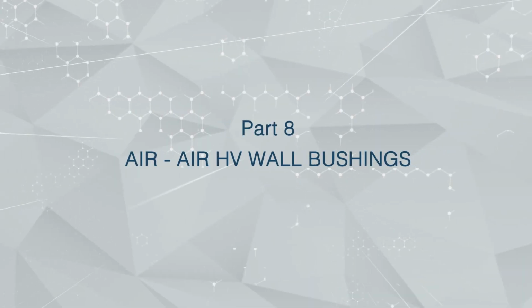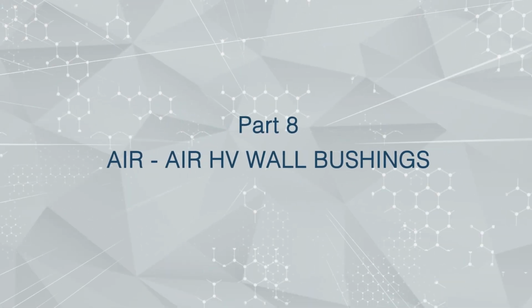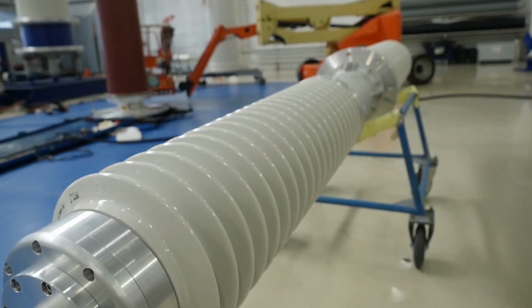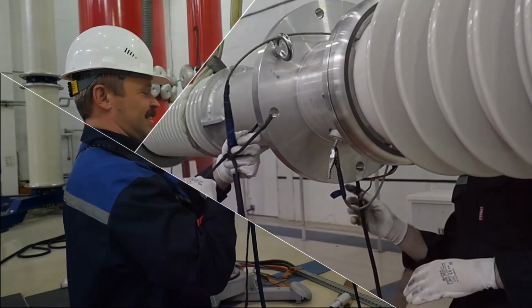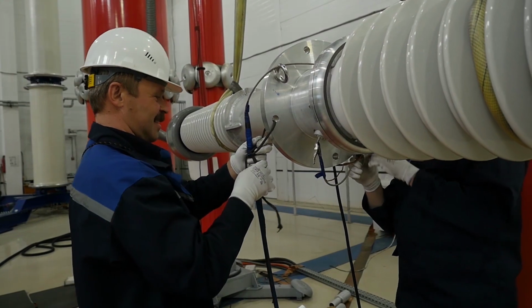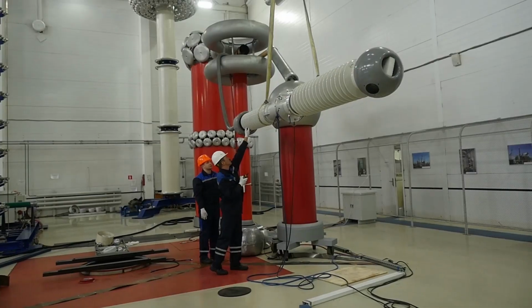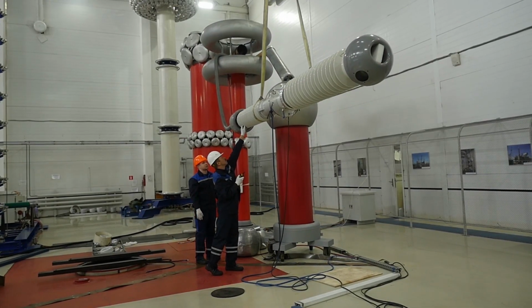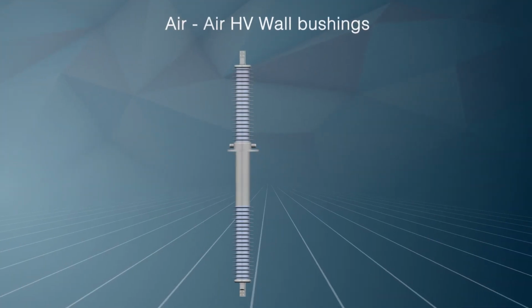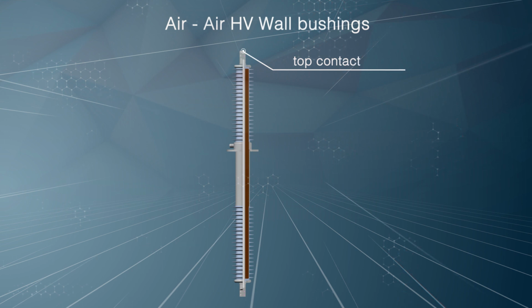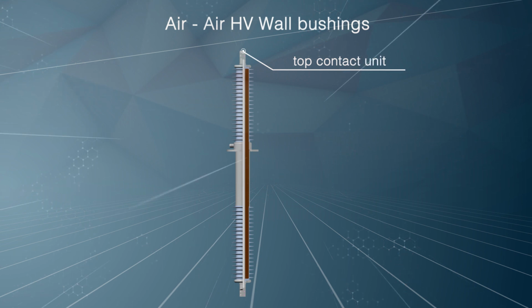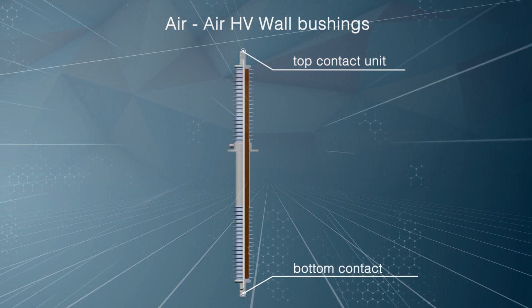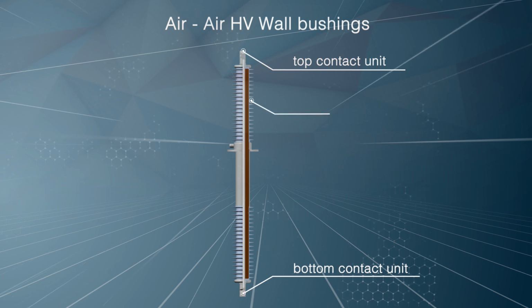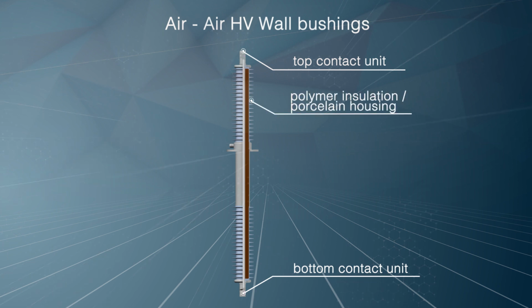Air-to-air high-voltage wall bushings. The bushings are intended for installation in walls and floor slabs of switch houses. Izolyator makes wall bushings only with condenser-type solid insulation core with RIP technology as the most effective. For a possible connection to any of the parts of the bushing, there are contact terminals installed on both ends. Air-to-air bushings can have a porcelain external insulation or polymer finning.